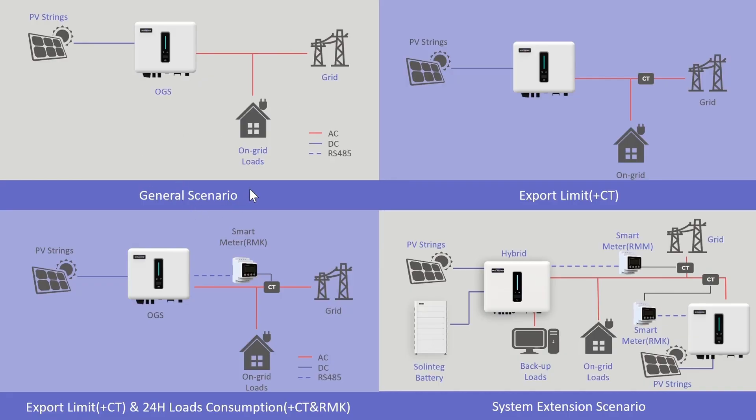Now let's come to the last part — application scenarios. The first is the general scenario: you need one inverter, PV string, loads, and grid. If you want export limiting, you need to add a CT. If you also want 24-hour load consumption monitoring, you additionally need a smart meter (the RMK). The last scenario is system extension: if you already have an energy storage system and want to add another PV string inverter, you can connect the two inverters together on the AC side, using two smart meters — one RMM for monitoring the hybrid inverter, and one RMK for monitoring the OGS. For more details, contact Solinteg technicians or visit Solinteg Academy. Thanks for listening.